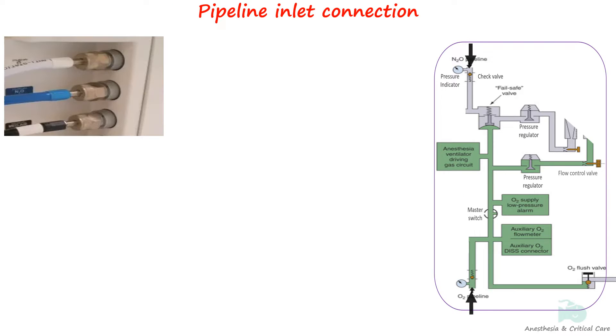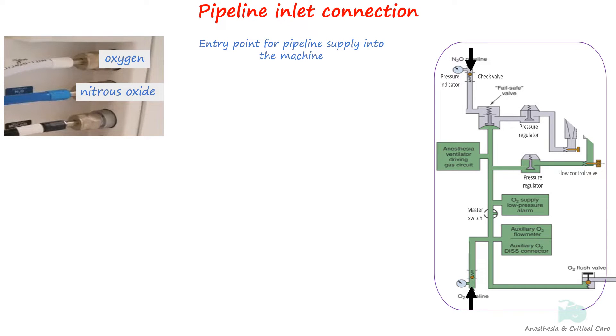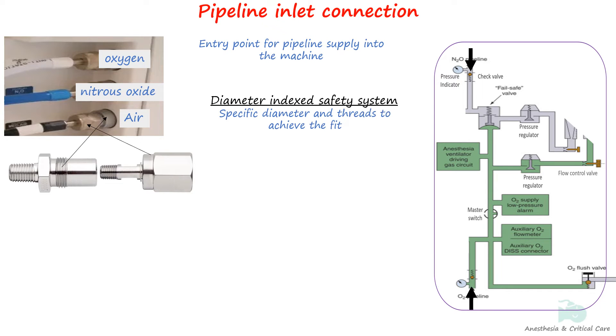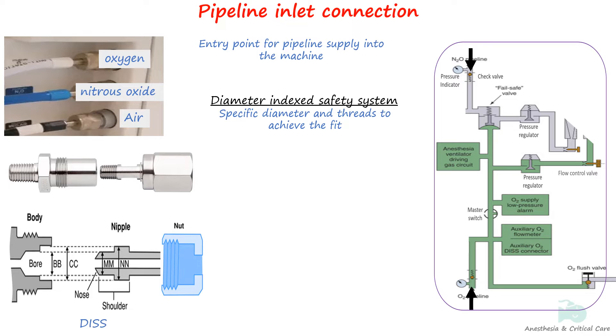The pipeline inlet connection is the entry point for gases from the pipeline supply. The anesthesia workstation standard requires pipeline inlet connections for oxygen and nitrous oxide. Most machines also have an inlet connection for air. These connections are fitted with threaded non-interchangeable connections called the Diameter Index Safety System, which consists of a body, nipple, and nut combination.